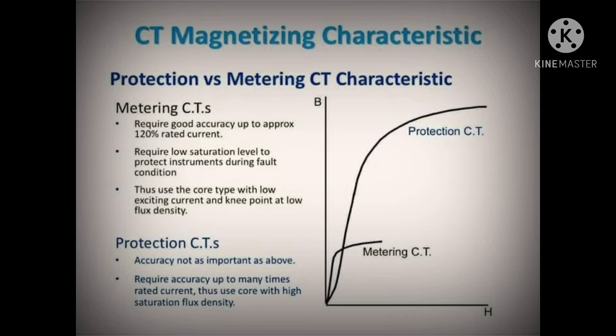Differential protection schemes should not trip on external faults. The magnetizing characteristics of both CTs used for differential protection must be the same, which means they have the same knee point voltage and the same excitation current at midpoint.